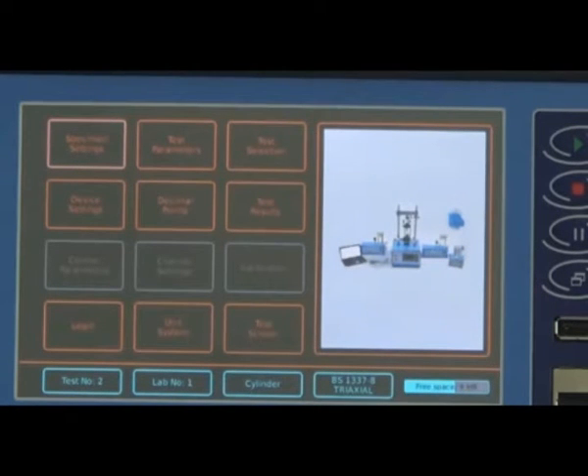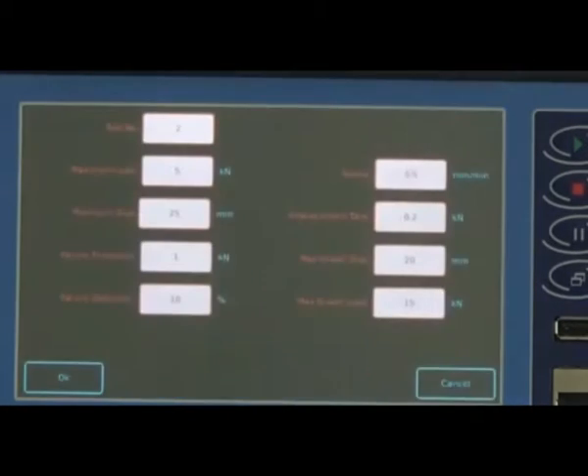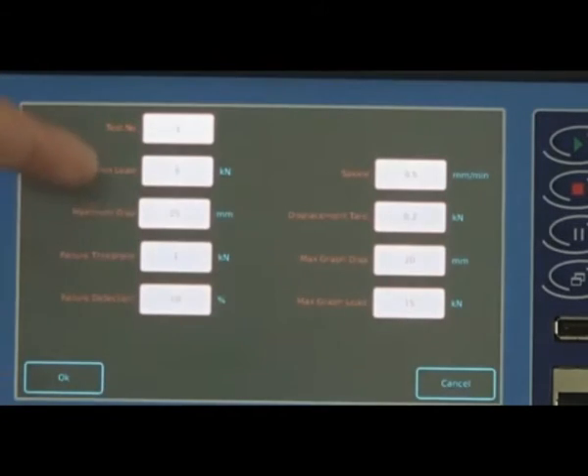The second menu is test parameters. The first option shows us the test number. We are entering the first test. And the second one is maximum load. And the third one is maximum displacement. And the fourth one is the failure threshold. And the failure detection is set as 10%.